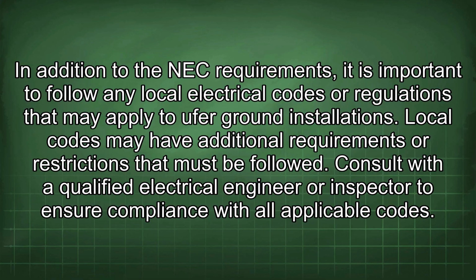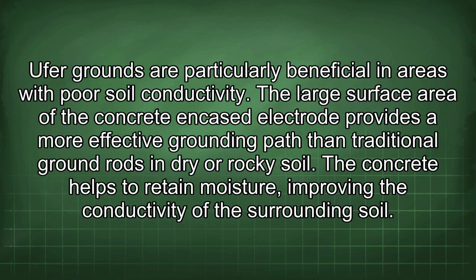Local codes may have additional requirements or restrictions that must be followed. Consult with a qualified electrical engineer or inspector to ensure compliance with all applicable codes. Ufer grounds are particularly beneficial in areas with poor soil conductivity. The large surface area of the concrete encased electrode provides a more effective grounding path than traditional ground rods in dry or rocky soil. The concrete helps to retain moisture, improving the conductivity of the surrounding soil.